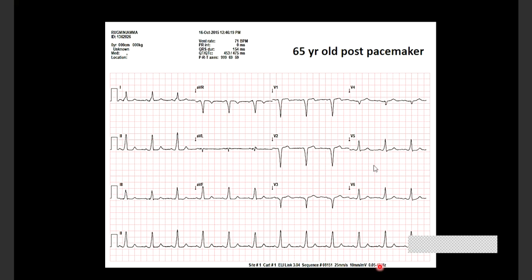Generally, very sharp, rapid signals, like pacemaker spikes or QRS notches, are high frequency signals. QRS notches, J waves, and pacemaker spikes qualify as high frequency signals. So they usually are more than 40 hertz. So if your ECG setting is 40 hertz, you will miss all these signals, all these interesting things on the ECG. The American standard or any standardization says the low pass filter should be a minimum of 100 to 150 hertz, not 40 hertz. But unfortunately, most ECG machines today have 40 hertz as a low pass filter setting. This is unfortunate.